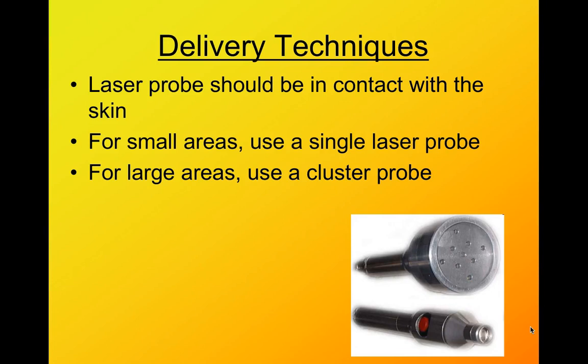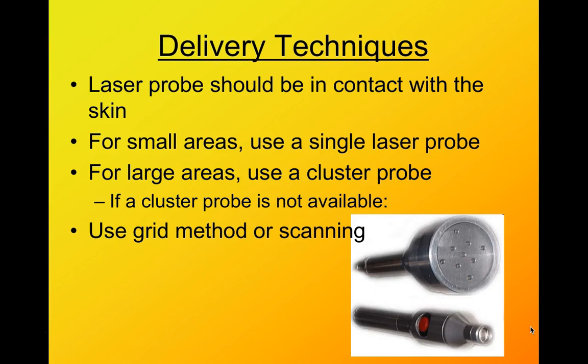For small areas, you can use the single laser probe, which we see here. And then for larger areas, we can use these clusters, which again means that each of these is a diode sending out an individual laser beam. If the cluster probe is not available and we're trying to treat a slightly larger area, then we have to do either what we call the grid method or the scanning method. For a grid, we take the size of our laser probe, usually about 1 centimeter squared, and we grid out 1 centimeter squared segments. We do a treatment, move to the next spot, move to the next spot.